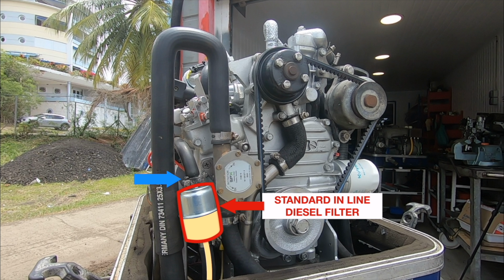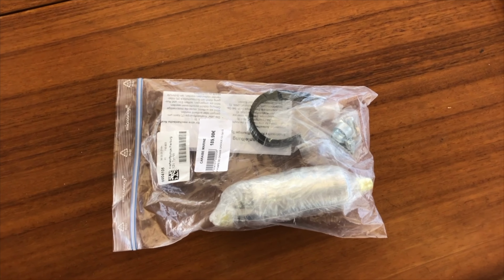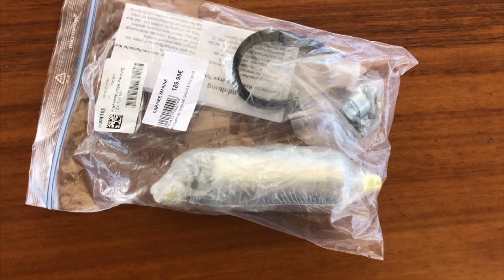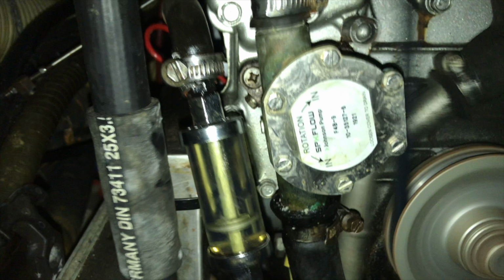The problem is that when you stop, it might flow back, leaving this filter more or less empty, and you don't even see this. Then, with an empty filter, you put the hose back on again, and of course it will not start because there is no diesel here. Even trying to start it 8 to 10 times will not help you, because the feeding pump is basically a very slow working pump, and still you have no idea what the status is here. As the diesel pump is failing so much, having a visual overview like this will save you lots of time and frustration.